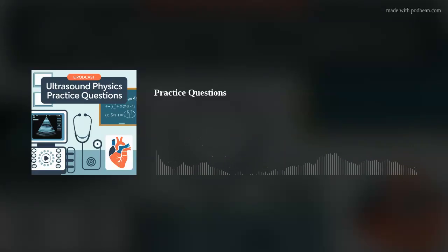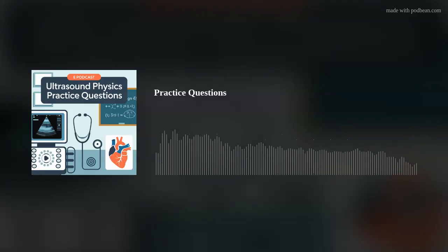That's pretty cool. This one's about a device used to measure the intensity profile of an ultrasound beam. What is that device and why is it important? That device is called a hydrophone. It's essentially a microphone designed to pick up those ultrasound frequencies, kind of like an underwater microphone. So it's like a microphone for sounds we can't even hear. What do we use it for?